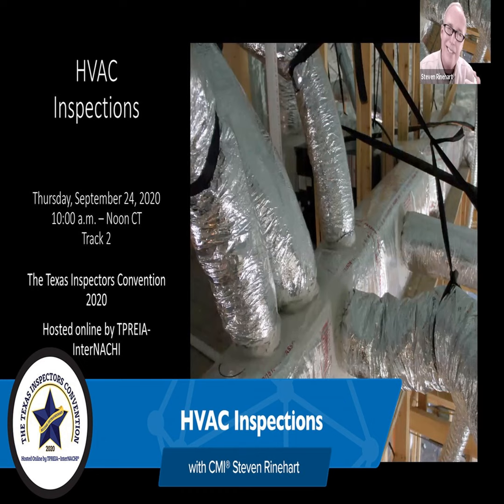Okay, Steve, we got a couple questions here we can run by you. What's a proper way to have a sediment trap installed? Is that a trick question? I've seen guys posting them upside down, sideways, but typically it just comes down, and just before the transition from the flex connector into the rigid, say at an air handler, you'd have, I think it's in the manufacturer's instruction, it'll show that little drip leg.